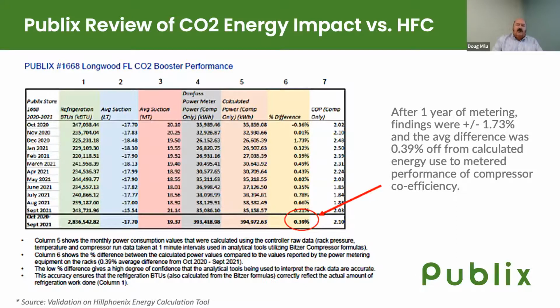But at this particular store, we learned when we looked at total heating degree days versus cooling degree days, Central Florida really doesn't have many heating degree days. They're mostly cooling degree days. So with higher mean average temperatures, we're seeing at this particular store, which is about 11 miles north of Disney World, if that gives the audience perspective where we're at, it's usually hot. And if it's not hot, it's wet. And then you get a combination of both. So it's kind of like a swamp, if you will. But with that, we're probably averaging about 4% higher energy from a traditional HFC store of similar size and location.